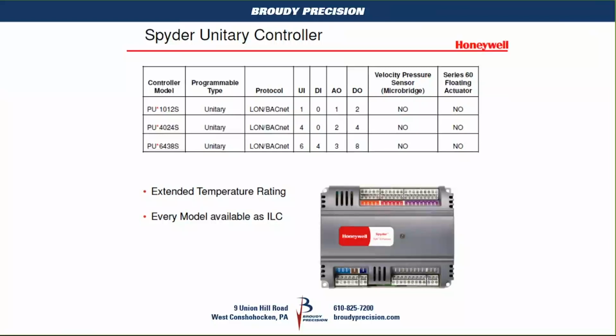Now the Spyder Relay also has more capacity for programming, and it is the only Spyder that you can use with the extended I/O modules, the Sylk I/O module. So if you're putting a Spyder on a job that exceeds the point count that you see on a 6438, you may add on; there are 3 flavors of Sylk I/O modules. You would have to use a Spyder Relay unitary controller for that. They don't make a Spyder Relay in VAV, so it only comes in the unitary. It comes in ILC, and it comes in BACnet as well.